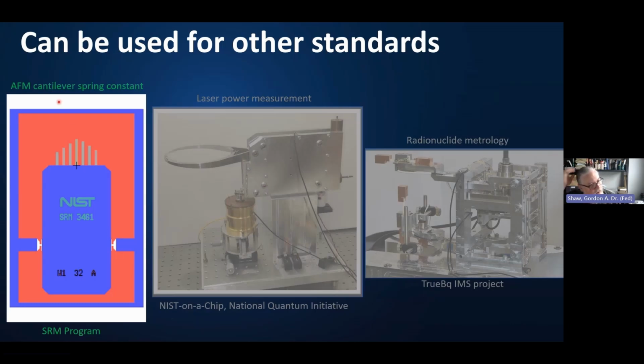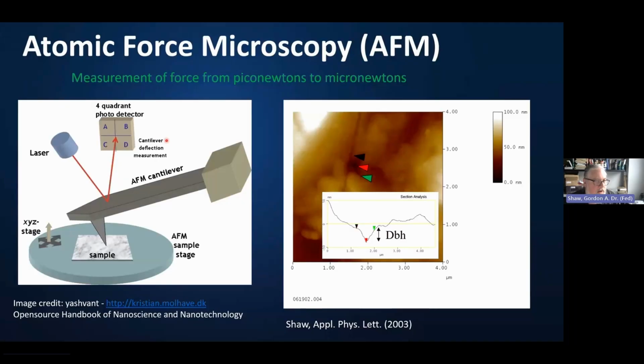a standard reference material that was developed here at NIST for atomic force microscopy, or AFM. The atomic force microscope is an instrument that uses a microfabricated force sensor with a sharp tip that is brought into contact with a sample surface. The forces between the sharp tip and the sample allow us to either map the surface topography with nanometer scale resolution, or to apply very small forces from piconewtons to micronewtons on the sample to measure mechanical properties at the nanometer scale.